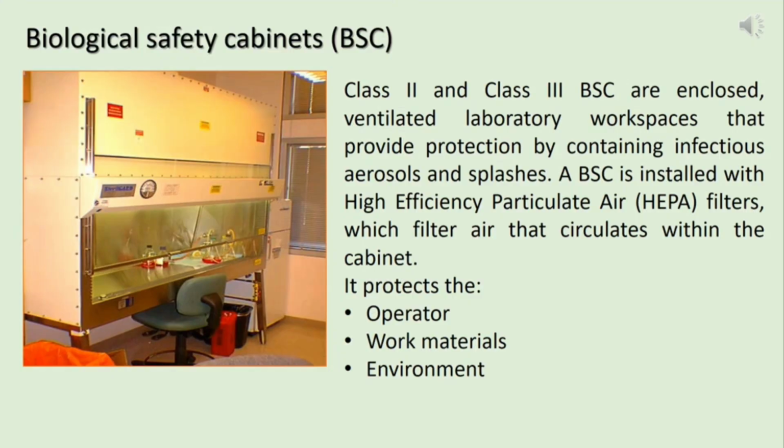Biosafety cabinets are enclosed, ventilated laboratory workspaces, and they are designed to contain infectious aerosols and splashes within the cabinet. These BSCs are installed with filters called HEPA filters.